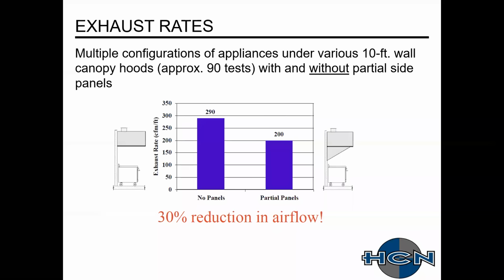But in reality, anytime you have a wall canopy hood, a back shelf hood, I mean, typically for most manufacturers, back shelf hoods are integrating end panels to begin with. But anytime you do a wall canopy hood, you should really be using end panels. So hopefully, just seeing some of those things that you saw right now, we should really start integrating end panels for pretty much every kind of wall canopy design we do. Great, thank you.